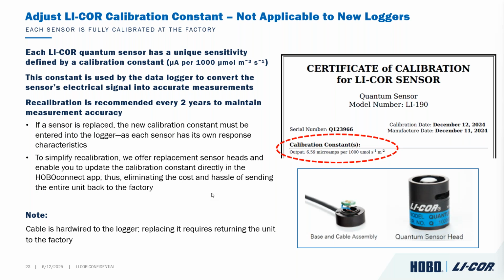So I think that is a great way of potentially eliminating the cost and hassle of sending the entire unit back to the factory. So if not interrupting your deployment is critical, 2 years down the line, what I would recommend is actually just getting one of these new sensor head from us. And I just wanted to clarify that the base and cable assembly is hardwired to the logger. So if for whatever reason you actually needed to replace the cable itself, the base and cable assembly, you would have to return the unit to the factory. So again, nothing you would have to worry about for brand new products, but figured I'd mention it, and this is something you would be needing down the line.